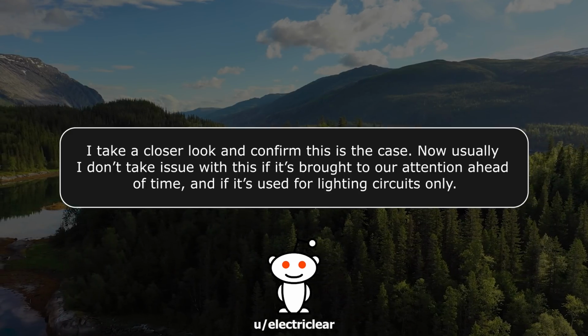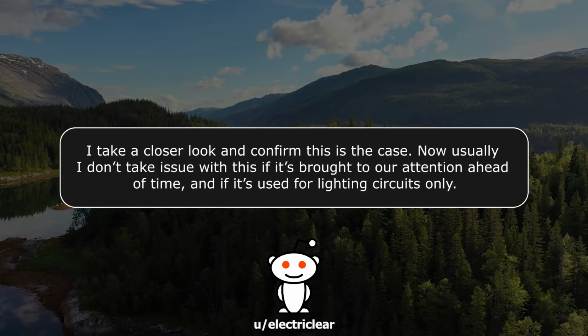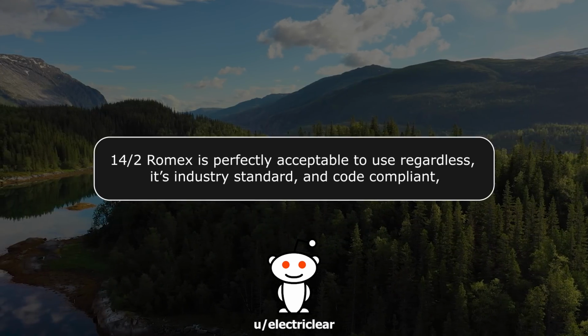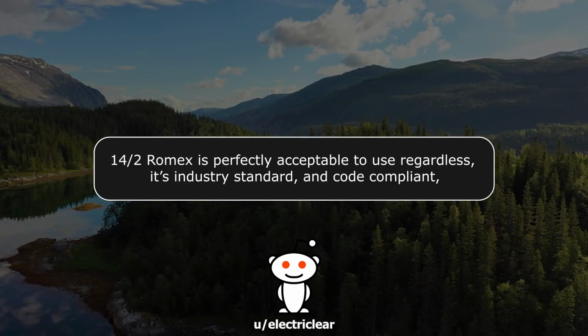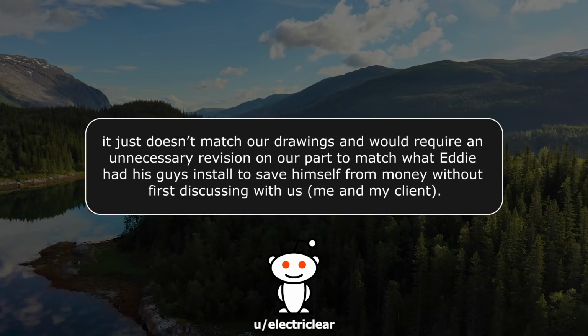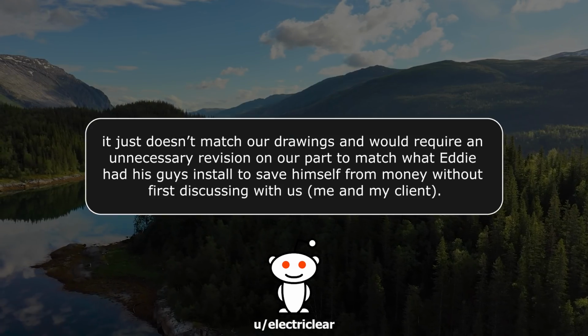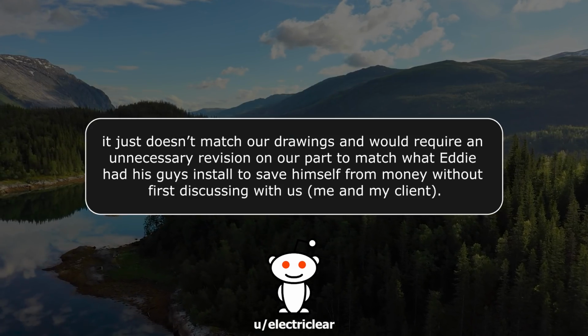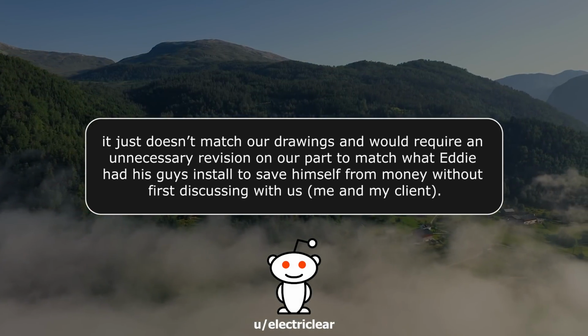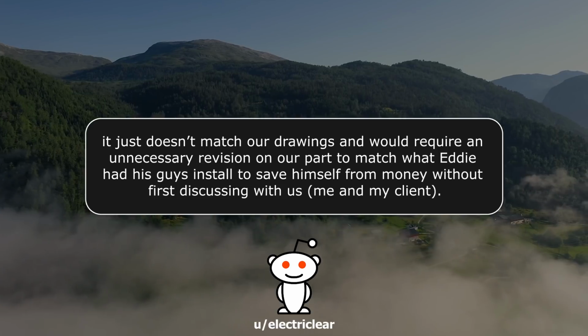Now, usually I don't take issue with this if it's brought to our attention ahead of time, and if it's used for lighting circuits only. 14-2 Romex is perfectly acceptable to use regardless. It's industry standard and code compliant. It just doesn't match our drawings and would require an unnecessary revision on our part to match what Eddie had his guys install to save himself money, without first discussing with us, me and my client.